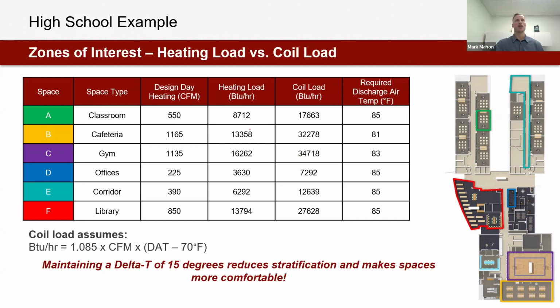And the reason for that is our heating load is assuming our space temperature is 70 degrees, and the temperature and energy exchange is occurring from a 70-degree space to our outside ambient conditions. While our coil load is needing to actually elevate the temperature of 55-degree saturated air all the way up to 85. So actually a much higher load than the heating load needed for the space. That's actually a step that I see missed in some plans from some engineering firms. I'm sure that's not from anybody here, but something I would want to consider and throw out, that the coil load is much higher than the heating load for the building in each of these zones.